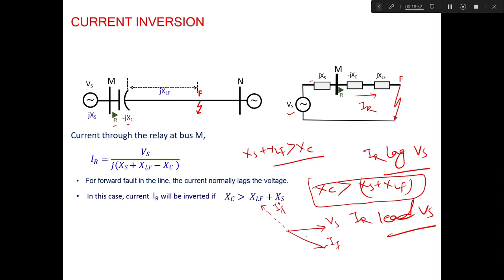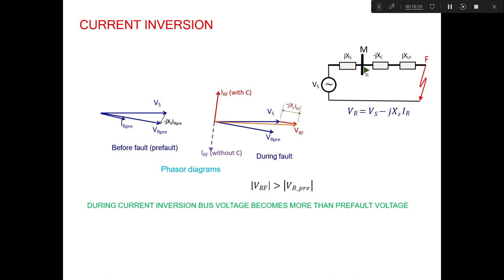When current inversion occurs, the relay sees a forward fault but declares it as a reverse fault, causing serious protection problems. During current inversion, the bus voltage VRF becomes greater than the pre-fault voltage VR, meaning the bus voltage becomes more than the pre-fault voltage during the inversion condition.